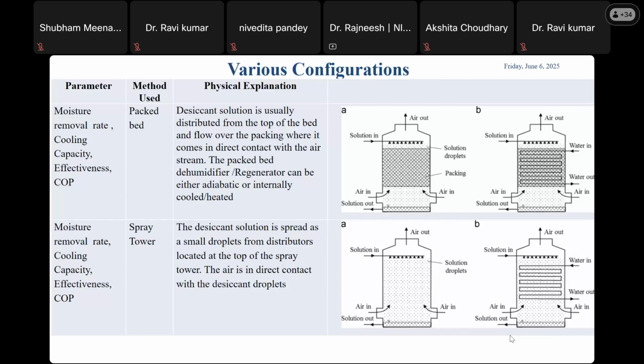Now this is the liquid desiccant. In liquid desiccant, the solution is a mixture of water and desiccant, known as the desiccant solution, which is generally distributed from the top of the bed and flows over the packing, where it comes in direct contact with the air and removes moisture from it. The solution is then collected in the basin.